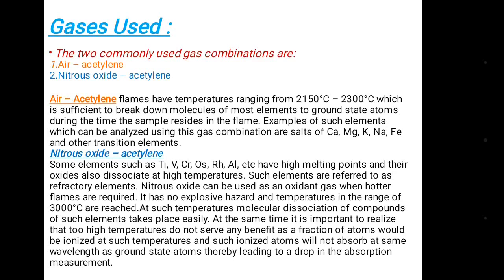Now, what are the gases used for the AAS instrument? Two commonly used gas combinations are air-acetylene and nitrous oxide-acetylene. Air-acetylene flames have a high temperature ranging from 2150 to 2300°C, which is sufficient to break down molecules of most elements to ground-state atoms.